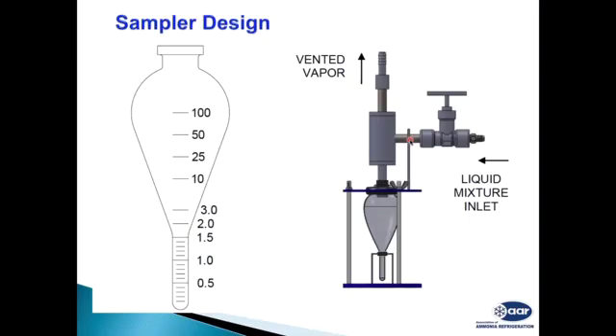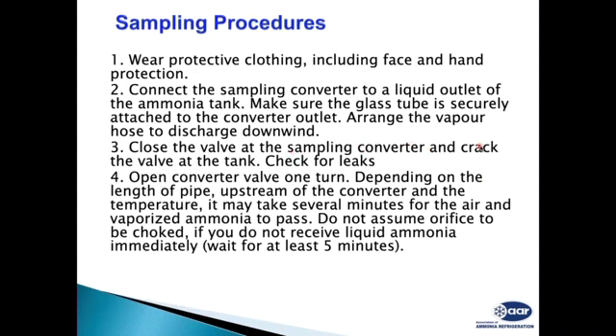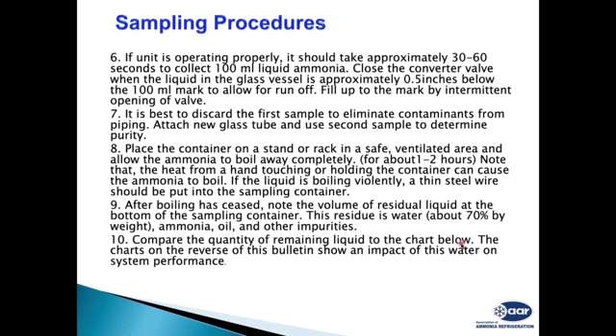Now, normally what we suggest is: close the valves of the sampler and crack open the valve. Open one turn only. Depending on the length of the pipe and the temperature upstream of the converter, it may take 5 to 10 minutes to get a sample. Always take out the first sample, put it aside, and take a second sample, so any contamination coming in will be drained. Normally it will take 30 to 60 seconds to get a 100 ml sample. Make sure you collect 100 ml, close the converter valves, close everything, and when it is at the 100 ml mark, turn it off.